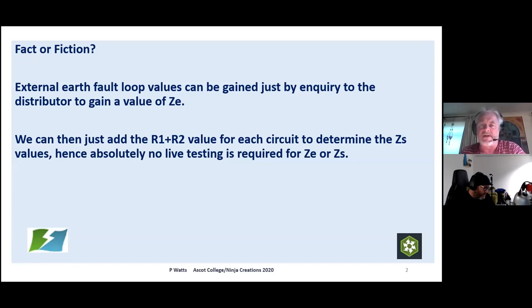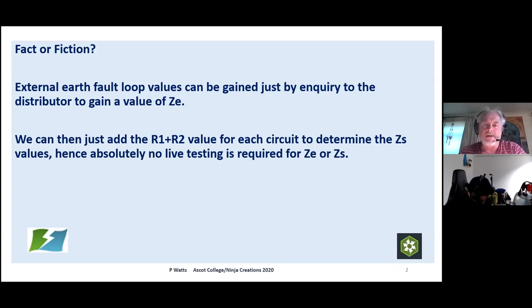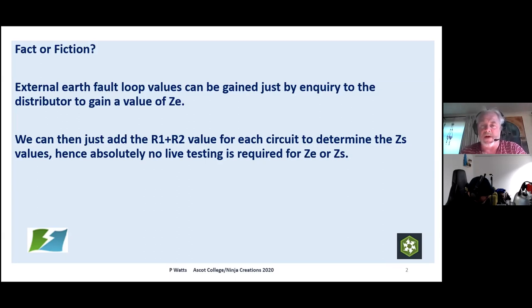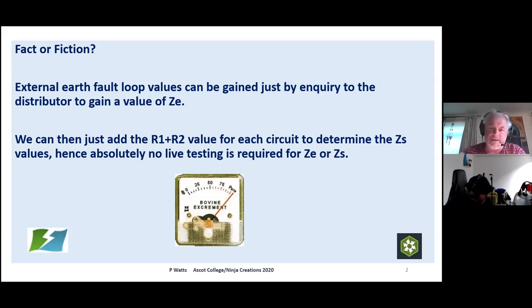We can do it all by calculation. We're told the earth loop values can be gained by inquiry from the distributor — that gives us our Ze — and then we can do our calculations of R1+R2, which we discussed on the previous calculation and testing webinar, to determine the Zs values, simply adding on the calculated R1+R2s to our Ze by inquiry. Certain people would have us believe that is absolutely fine. That's my comment on it — because that's what I think about it.